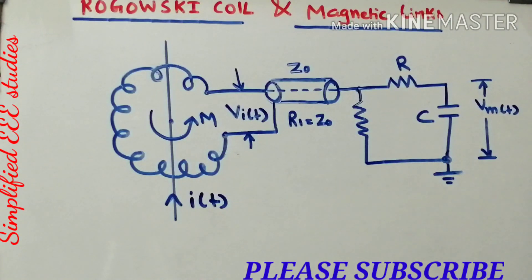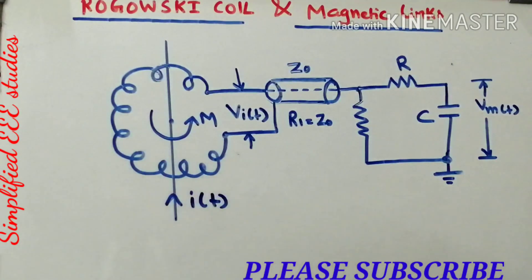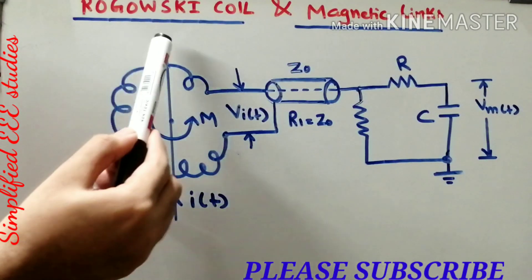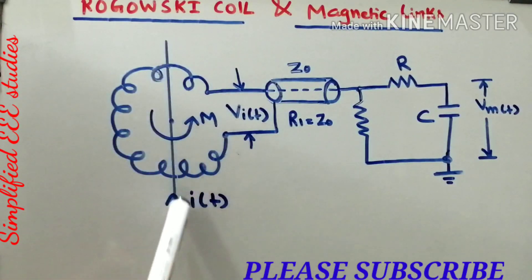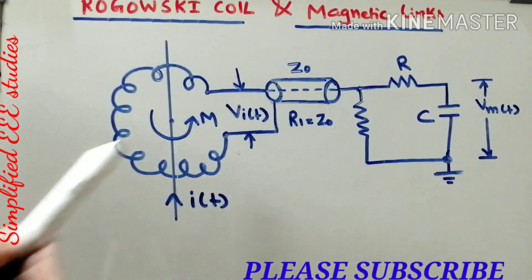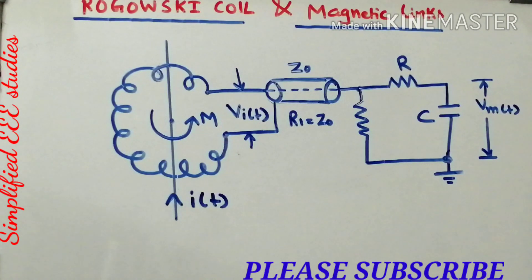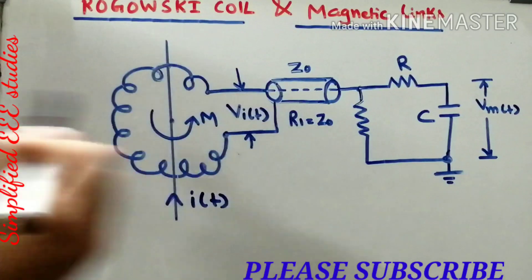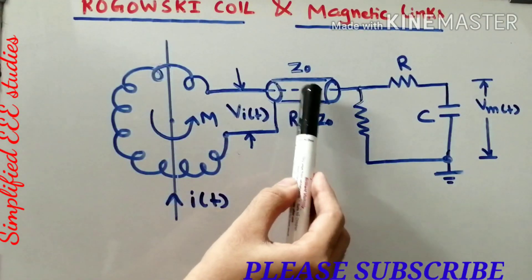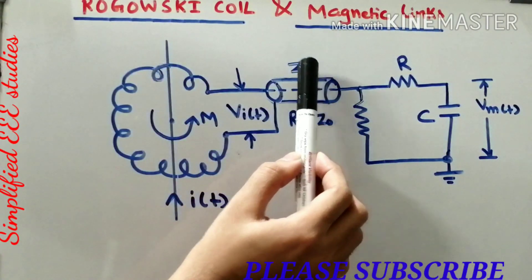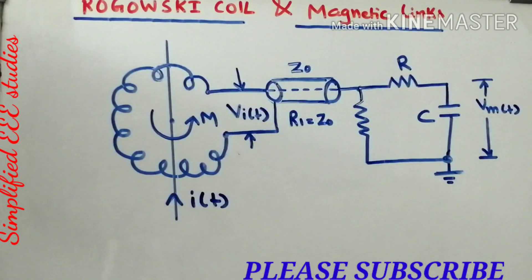Let us see the schematic diagram of the Rogowski coil for the measurement of impulse current. Here you can observe the current carrying conductor. I(t) is the current passing through it. The Rogowski coil is an inductor coil with a circular shape — basically a toroid. We also have a delay cable with surge impedance Z0, and a meter which may be a CRO or DSO.